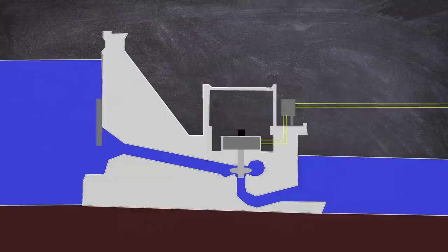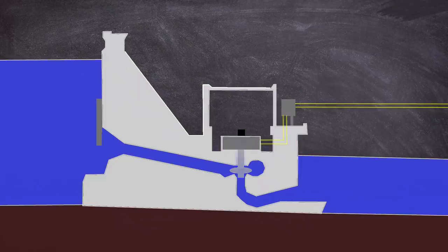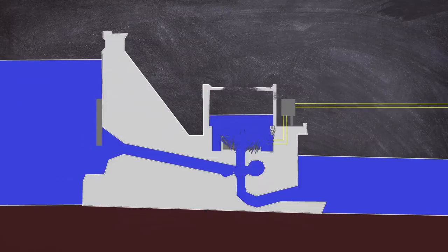The monumental amount of water then began gushing into the turbine hall, flowing over the other turbines and their generators, shorting them out in the process. The control room became aware of the disaster as unit 2's electrical power output dropped to zero, causing a local blackout. The water soon cut through the structural steel, and the turbine gallery roof collapsed. Workers were washed away out of the building down into the river. Some were later rescued, however others were sadly not. The steel gates to the water intake pipes of the turbines, weighing around 150 tons each, were closed manually. These were held up by hydraulic jacks. The process would take at least 25 minutes. All whilst this was happening, water continued gushing out of the destroyed unit 2.